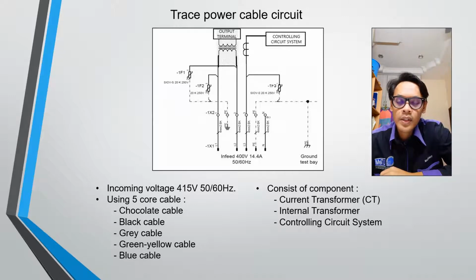For the frequency converter system, it uses a main supply of 415 volt to power up the system. It starts from the isolator switch, which is 415 volt, to the power terminal block inside the frequency converter. It uses 5-core cables which consist of brown cable for phase line 1, black cable for phase line 2, grey cable for phase line 3, green-yellow cable for ground and PE, and blue cable for neutral.